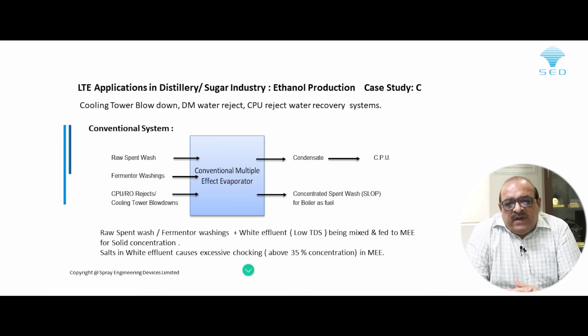Dear friends, you must be aware, this is a very common phenomenon which we are using. Everywhere we want to remove the solids, we want to concentrate the solids, we dump everything in one standalone evaporator, and that increases our pain area. We are taking raw spent wash, fermenter washings, CPU RO rejects, cooling tower blowdowns, mixing them and feeding to the conventional evaporator system. The condensate which we are getting, we feed to the CPU for further polishing and recycling back to the system. And the concentrated spent wash which we are getting, we feed to the boiler as a fuel.